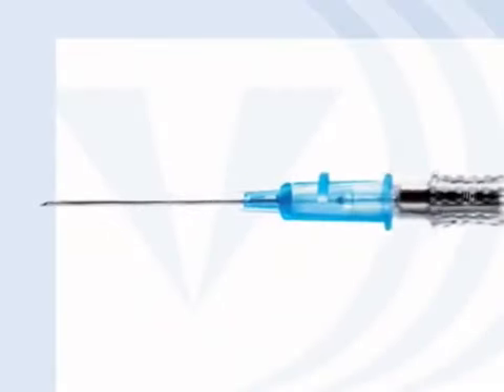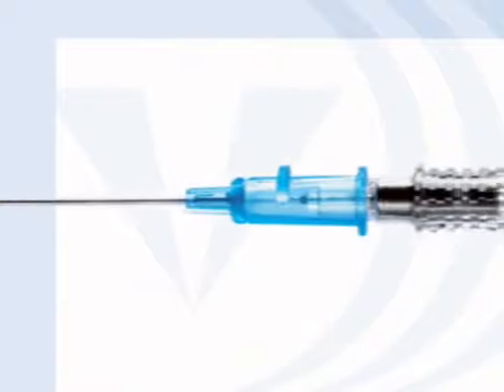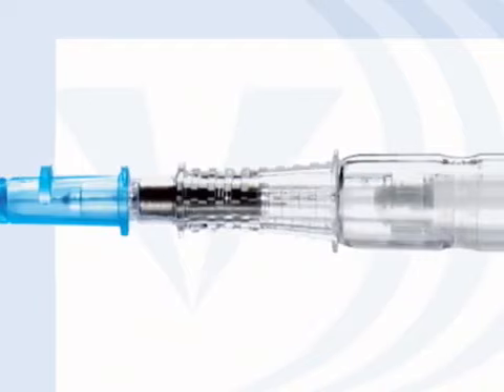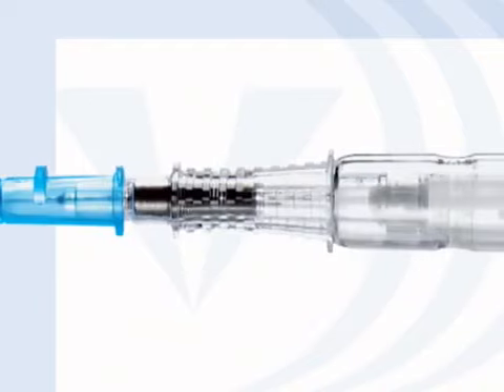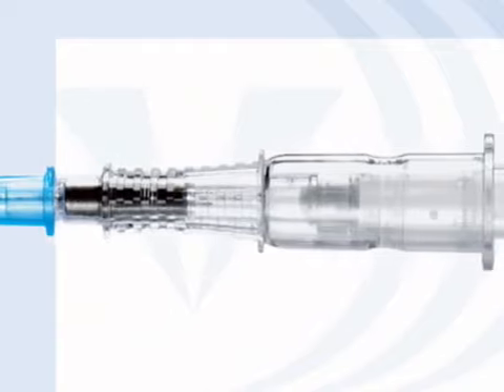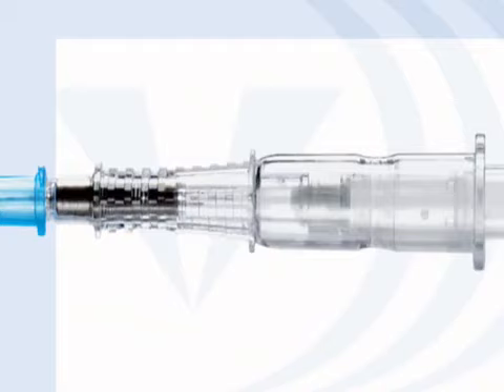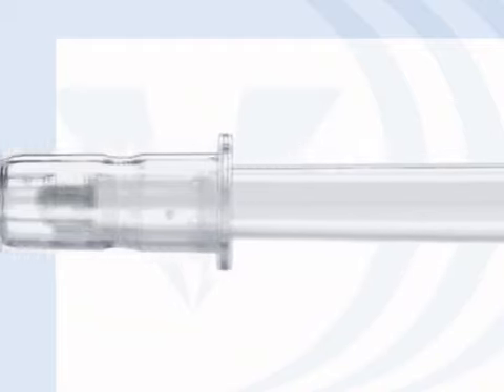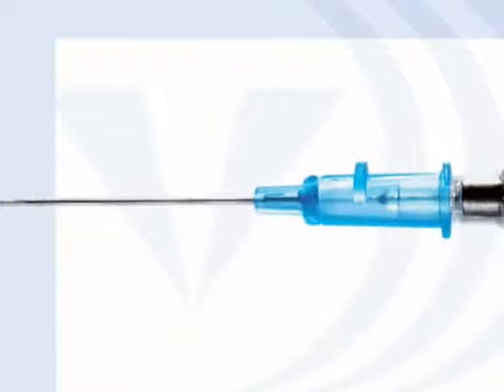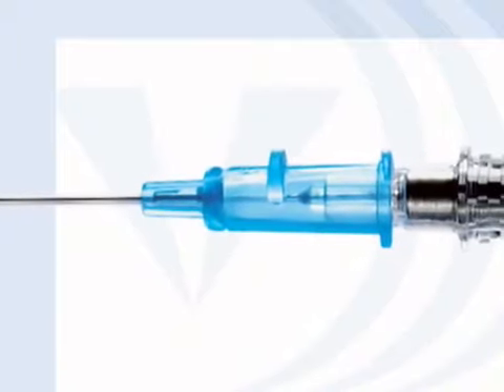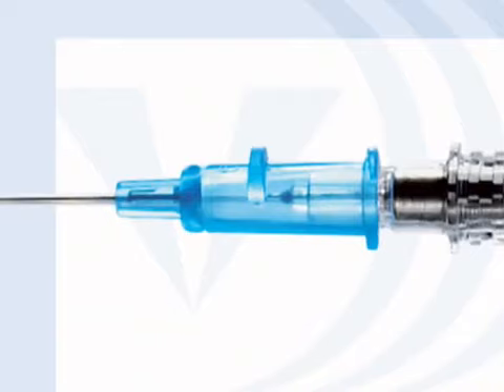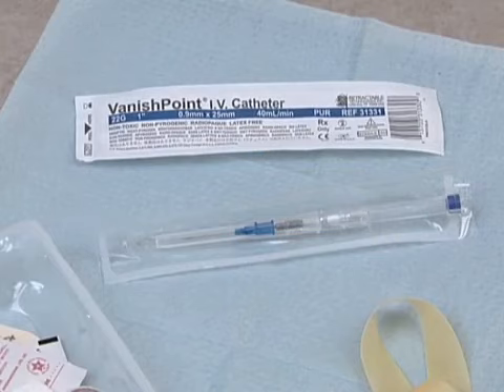The VanishPoint IV catheter is composed of an introducer needle and housing, which includes a retraction mechanism within the housing and finger grips for pulling back on the housing to activate the retraction. The finger grips and flashback chamber are clear to allow for flashback visualization. The end of the housing is color-coded to indicate the catheter gauge. The catheter hub is also color-coded according to international standards to indicate catheter gauge. The push-off tab facilitates one-handed hub advancement and indicates bevel orientation. Now, let's take a step-by-step look at using the VanishPoint IV catheter.